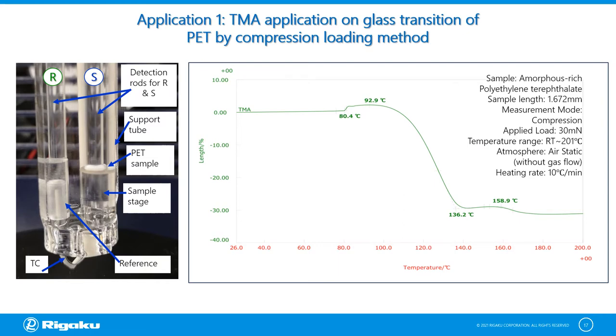This application shows the TMA measurement of PET material by compression loading method, measured from room temperature up to 200 degrees centigrade with an applied load of 30 millinewtons. A sudden increase in expansion is observed from 80 degrees centigrade due to glass transition of PET. During glass transition, the sample condition is soft and rubbery. Since a load is applied, instead of observing expansion from 93 degrees centigrade, the result reveals shrinkage up to 136 degrees centigrade — the detection rod has crushed the sample. Then at 159 degrees centigrade, a shrinkage on the PET sample reveals volumetric shrinkage.